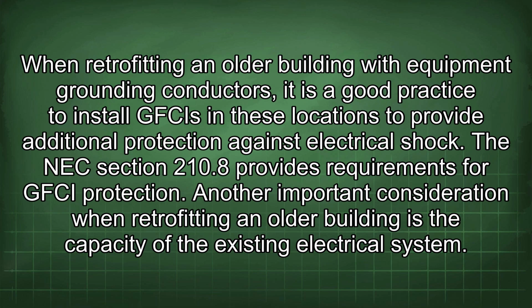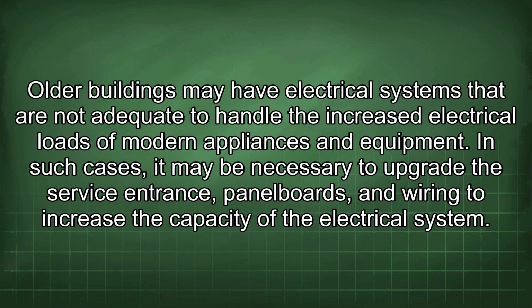The NEC section 210.8 provides requirements for GFCI protection. Another important consideration when retrofitting an older building is the capacity of the existing electrical system. Older buildings may have electrical systems that are not adequate to handle the increased electrical loads of modern appliances and equipment. In such cases, it may be necessary to upgrade the service entrance, panel boards, and wiring to increase the capacity of the electrical system.